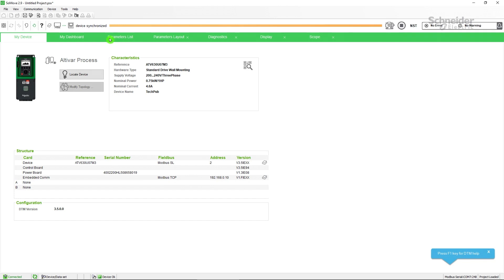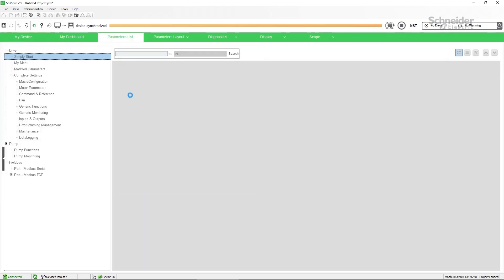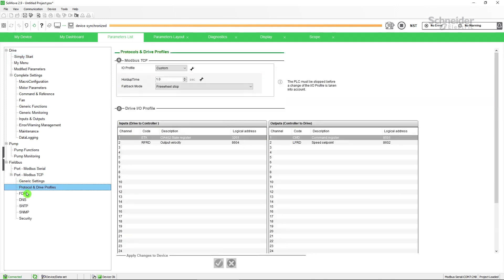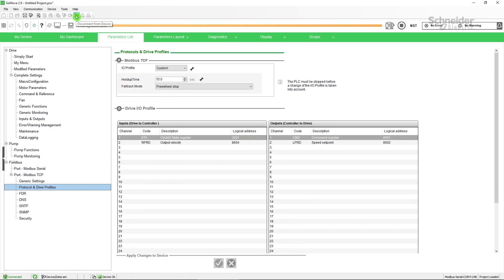For Ethernet, go to the Parameters List tab. On the Fieldbus menu, click on the Port MODBUS TCP drop-down menu. In Protocols and Drive Profiles, change the Holdup time. Click on Confirm to apply the change to the device. Disconnect SoMove and restart the drive.